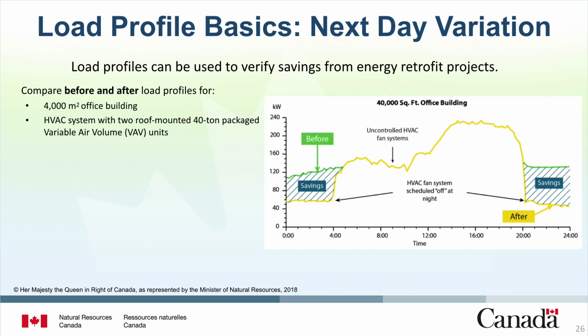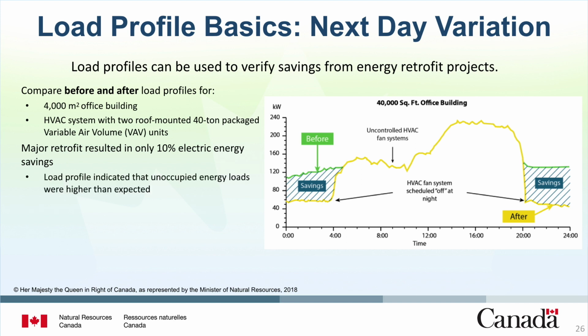Following a major HVAC, lighting, and control system retrofit, the energy manager was surprised to find that the post-retrofit electric energy savings was only 10% rather than the projected 23%. The renovated building's load profile indicated that unoccupied energy loads were higher than expected. Based on this information and her experience, the energy manager suggested that the HVAC fan system was operating 24 hours per day.